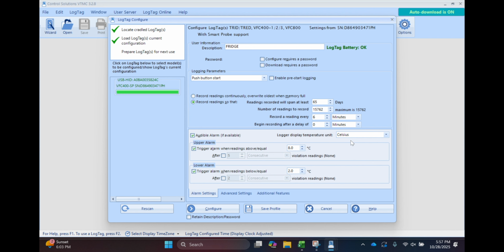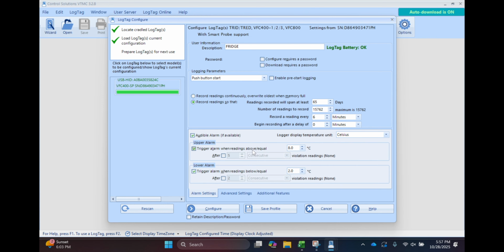While you must change every logger from Celsius to Fahrenheit, the software only needs to be changed once, not per logger. So continuing my configuration for a fridge in Celsius, I'm going to validate that my display is in Celsius, my audible alarm is still checked, my alarm is enabled, trigger alarm when readings are above or equal to 8 degrees Celsius, trigger alarm when readings are below or equal to 2 degrees Celsius.